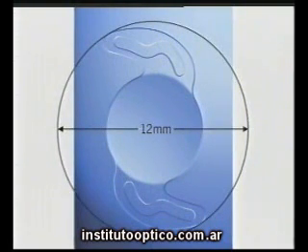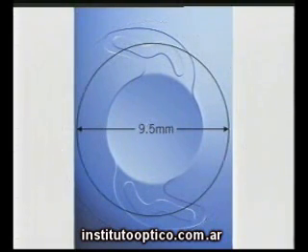The overall diameter of the lens is 12mm, and this can reduce to 9.5mm with haptic compression. The unique haptic design incorporates Rayner's patented AVH technology, which has been fashioned to resist excessive or asymmetrical capsular contraction. This provides the benefit of increasing support for the lens as the capsule contracts.